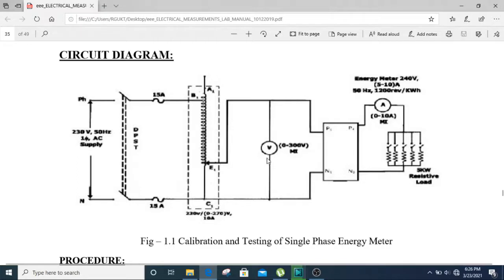Then we can find the true energy with the help of the voltmeter, ammeter and time measured by the stopwatch. V into I into 1. Here we use a resistive load, which means the power factor will be equal to 1. Voltage into current into power factor 1. That is, voltmeter reading into ammeter reading into 1 gives power. Power into the time taken by the energy meter to complete 10 revolutions. Power into time will be equal to energy. So we can measure true energy with the help of voltmeter reading, ammeter reading and time measured by the stopwatch for 10 revolutions.